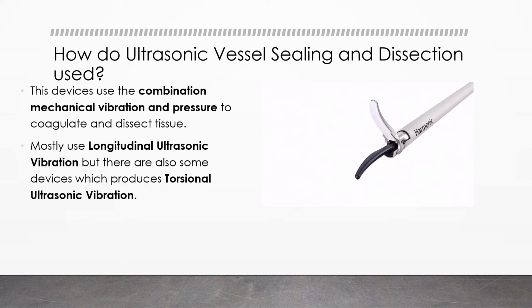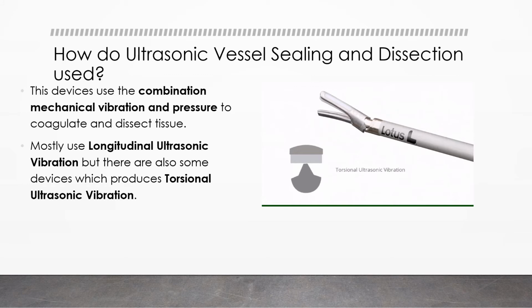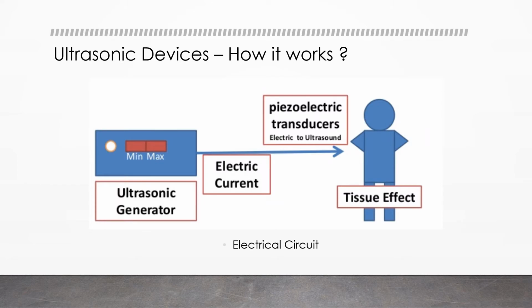How are ultrasonic vessel sealing and dissection used? This device uses a combination of mechanical vibration and pressure to coagulate and dissect tissue. Most use longitudinal ultrasonic vibration, but there are also some devices which produce torsional ultrasonic vibration. Next is the ultrasonic device. This is how we can see how it works.